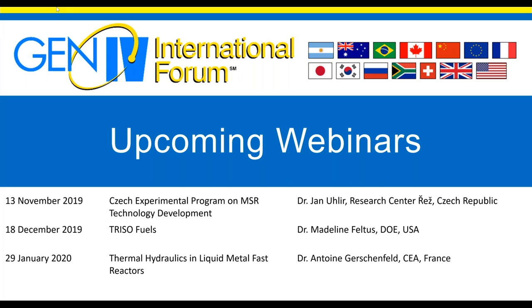You mentioned at some point that passive decay heat removal systems have been considered. Is this common in the design of these systems? Well, it's been common in the plants that have been under consideration in the U.S. for a long time. As I pointed out, these reactor cavity cooling systems are not new. They've been around for years. In the GE PRISM design and the GA MHTGR designs, these have been there from the get-go. And in the Framatome design, I know it's been in there for a while. So these concepts are not new. The idea with the work we were doing was to take them and perform testing on them to verify that they would operate according to plan and to provide the information needed to get them licensed with the NRC. So that was the intent of our work.